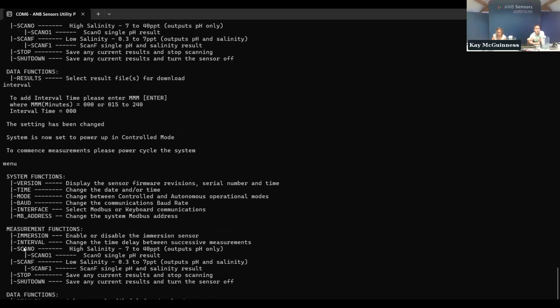And then we have our scan commands. So we have a scan O and a scan F. And these are currently for higher salinity waters and lower salinity waters. We also have an O1 and an F1, and that's if you want just to get one single measurement back and then to put the sensor to sleep in between. So again, this is for kind of the power consideration, isn't it? Yeah, exactly. So we have customers now that have written terminal programs where they send a scan O, they power the sensor up, send a scan O1 command, it delivers a pH number back, and then they just turn the sensor off until their next measurement cycle. And as Kay said, it's all around power management of the sensor and of the whole platform.